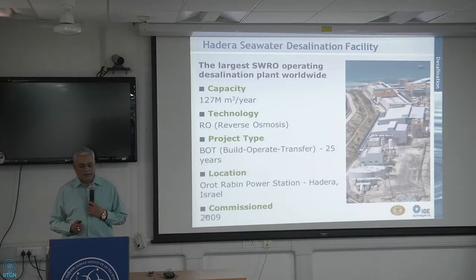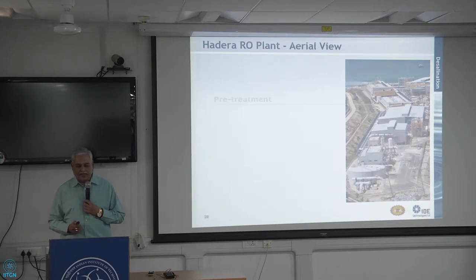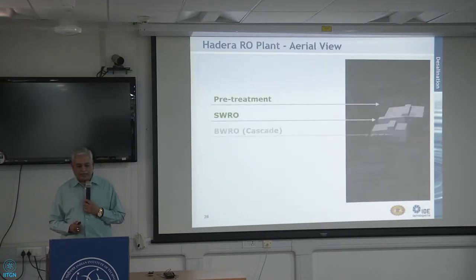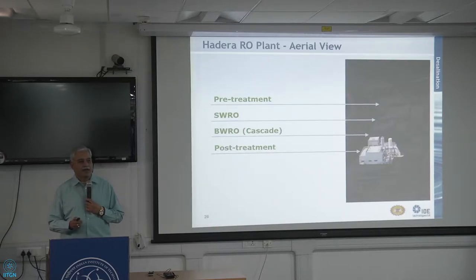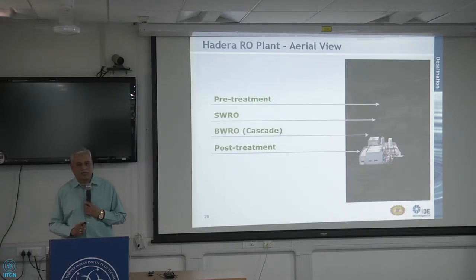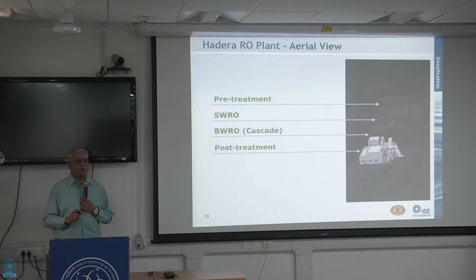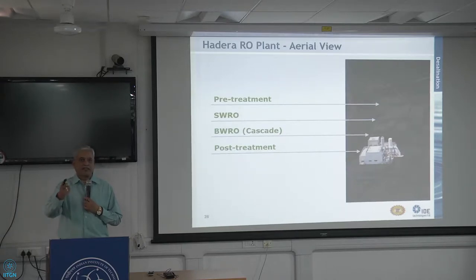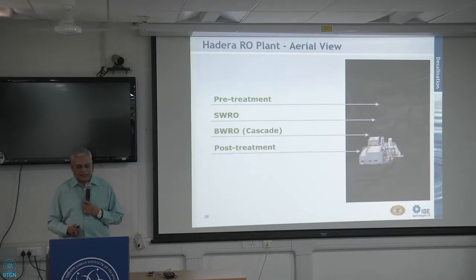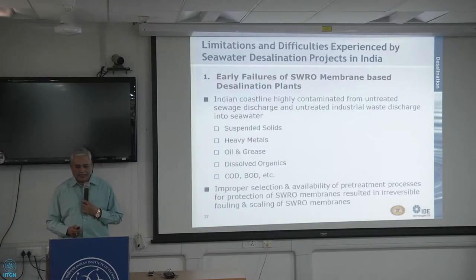This is among the world's largest SWRO plants, operating at almost 500 MLD in Hadera, Israel. The functional blocks include a pre-treatment building, an SWRO building, and a second-stage brackish water RO. Seawater has about 40,000 ppm TDS; one stage of SWRO reduces it to around 400 ppm. To further reduce to around 100 ppm — typical of river water — a second-stage brackish water RO is required. There is also post-treatment and a product water tank.